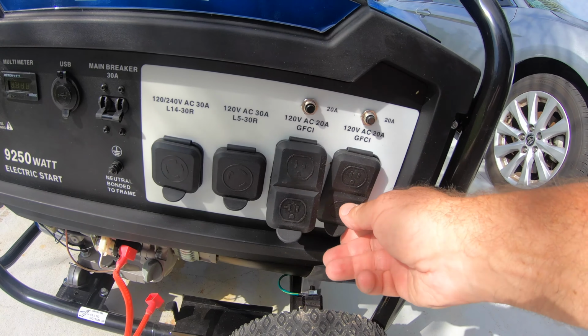Whenever we turned on the water heater, it would draw more than 25 amps and it would keep popping the breaker. So even though we had a generator and we were able to keep a lot of things running, we could not run our air conditioning and we could not have hot water, although we did have water, which was a big deal, and we could keep our refrigerator running until we ran out of gas and had to evacuate.